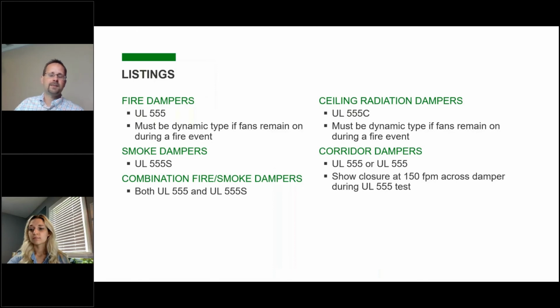Each different damper type has a specific UL listing. The important thing on this slide is not to memorize every single UL listing on here, but to understand that these UL listings are different depending on the type of damper. And the damper cannot be installed in a way that's different from its UL listed assembly. You can have no deviations. These are tested as a full assembly based on the details that are provided from the manufacturer, and deviations will violate that UL listing.